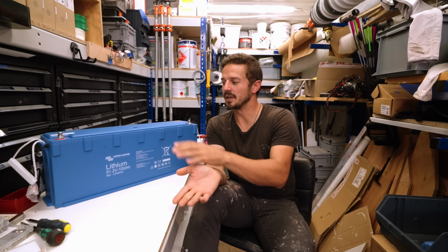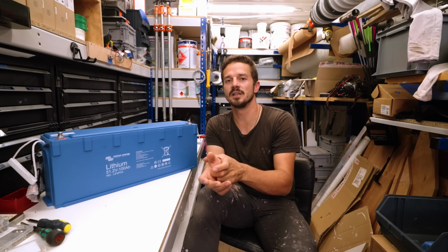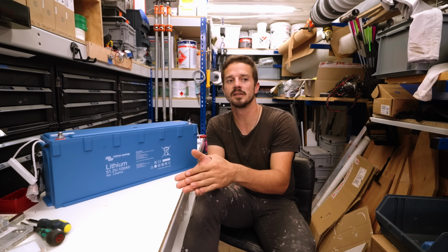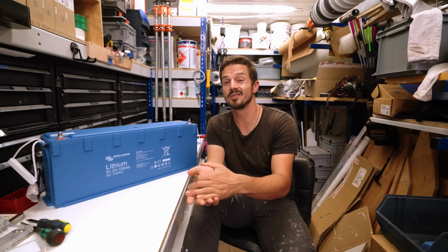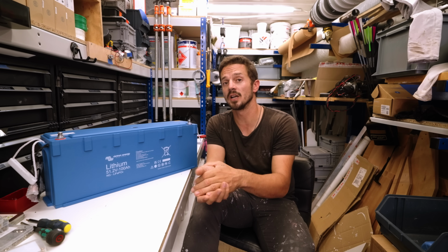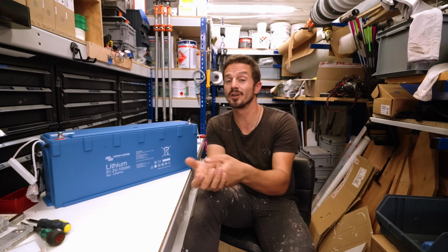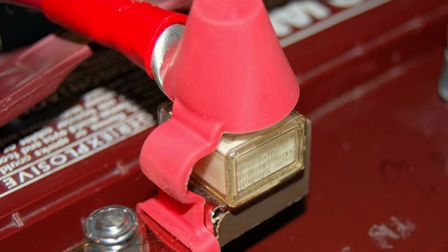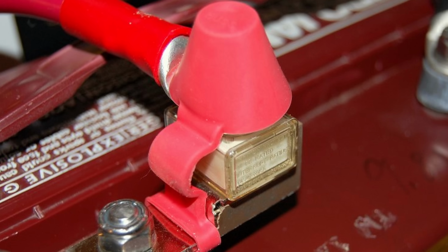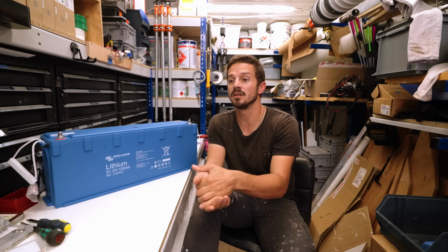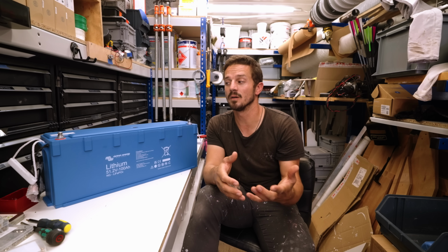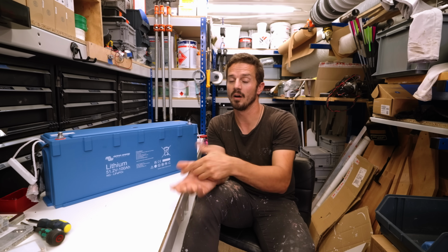There's no good off-the-shelf solution for what we need. Because these are lithium batteries, the fuses need incredibly high interrupting currents, and there's really only 1 fuse that does that well for the marine industry: a Class T fuse, which is a big chunky thing. We wish we could use terminal fuses that bolt directly onto the terminal, but they don't have a high enough interrupting capacity - they're meant for lead acid batteries, so we can't use them on lithium.